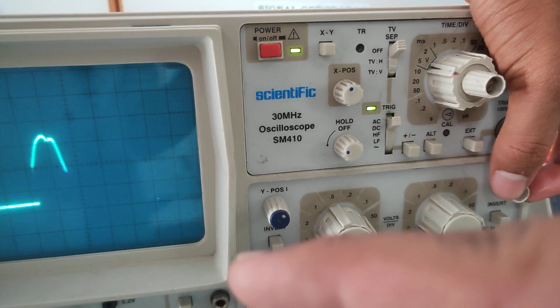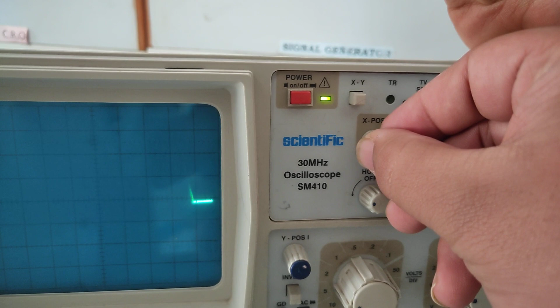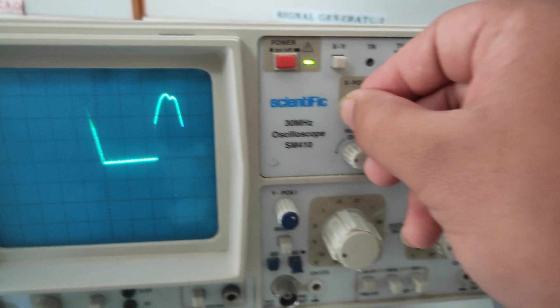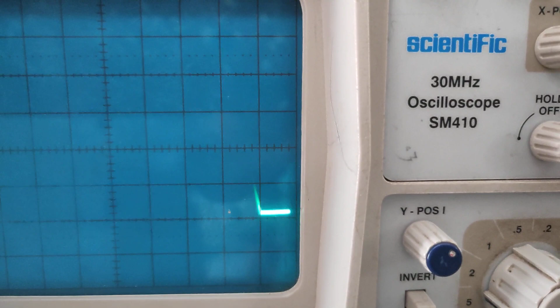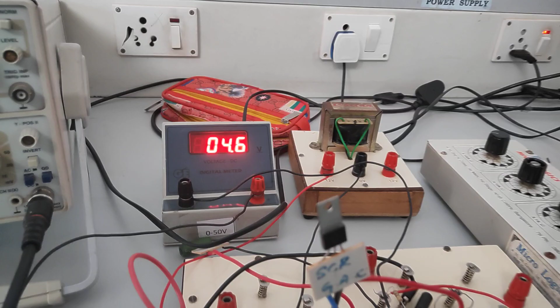Now you can see that the end of the positive wave has shifted, so first we adjust it to match the vertical line using the X position knob. Now if you check the firing angle, you can see we have exactly 2 divisions. Since one division is 18 degrees, 2 divisions is 36 degrees. For this firing angle, note down the corresponding voltage in the voltmeter, which is 4.6.